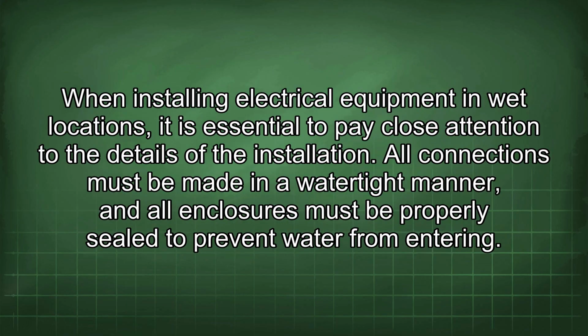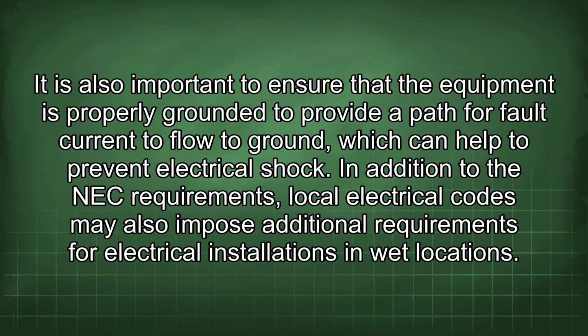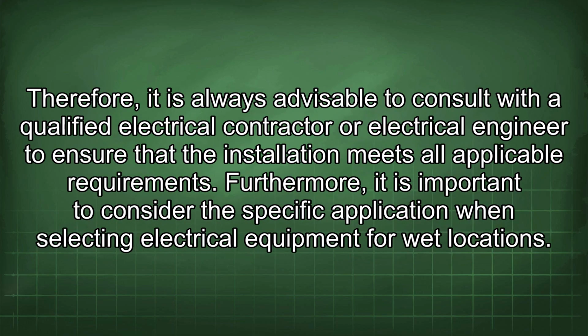When installing electrical equipment in wet locations, it is essential to pay close attention to the details of the installation. All connections must be made in a watertight manner, and all enclosures must be properly sealed to prevent water from entering. It is also important to ensure that the equipment is properly grounded to provide a path for fault current to flow to ground, which can help to prevent electrical shock. In addition to the NEC requirements, local electrical codes may also impose additional requirements for electrical installations in wet locations. Therefore, it is always advisable to consult with a qualified electrical contractor or electrical engineer to ensure that the installation meets all applicable requirements. Furthermore, it is important to consider the specific application when selecting electrical equipment for wet locations.